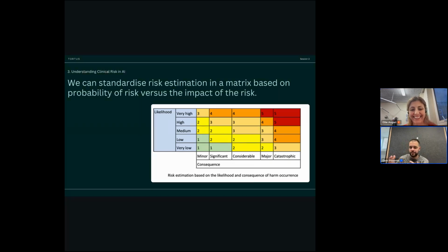And that's why it's useful to have, we're both CSOs, an external CSO, and to talk to the CSO in the hospital as well. One of the things to stress here is to make sure that when you're adopting a new technology, those hazard workshops that you're supposed to be doing actually do get done, because the subjectivity of what is and isn't significant can be quite variable, and your risk tolerance as an organization might not be the risk tolerance of the organization down the road, for example. And there are lots of inherent interesting things that can come out of those discussions anyway: use cases, intended use, better instructions, better training. So it's well worth doing as an exercise. Absolutely.